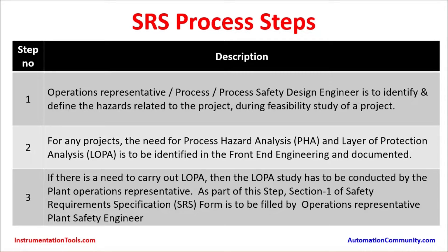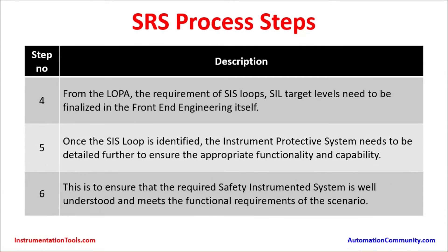During any project's initial front-end engineering phase, the process hazard analysis and layer of protection analysis must be identified. In step number three, if there is a need to carry out LOPA, the study must be conducted by the plant operations representative. As part of this step, section one of the safety requirements specification form is to be filled by the operations representative and plant safety engineer. In step number four, the requirements of SIS loops and SIL target levels are finalized from the LOPA document during front-end engineering.